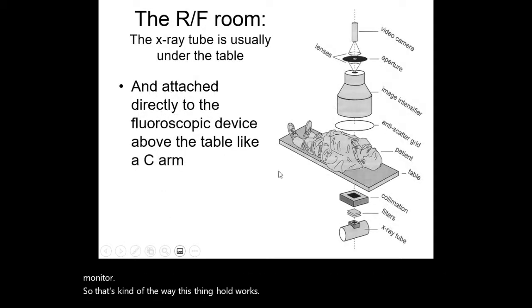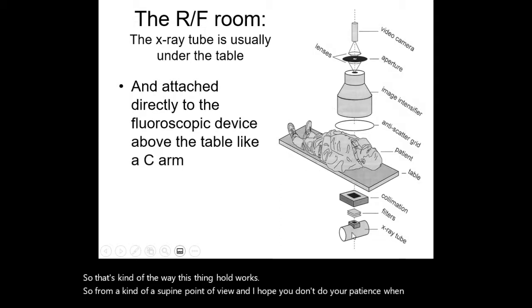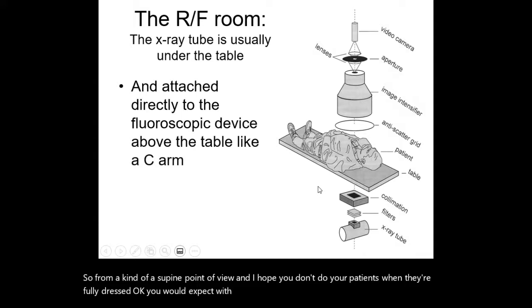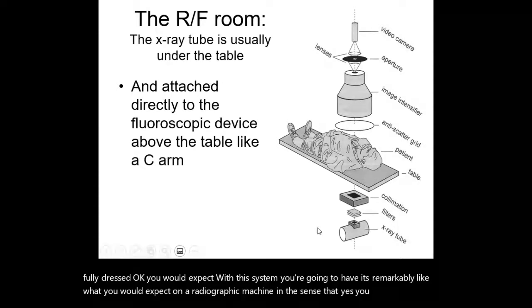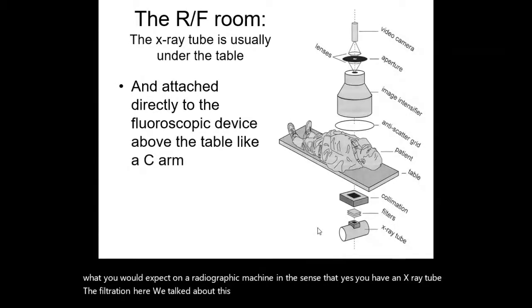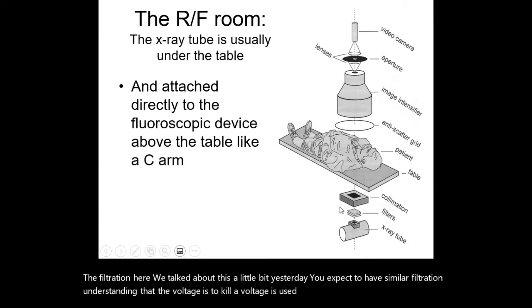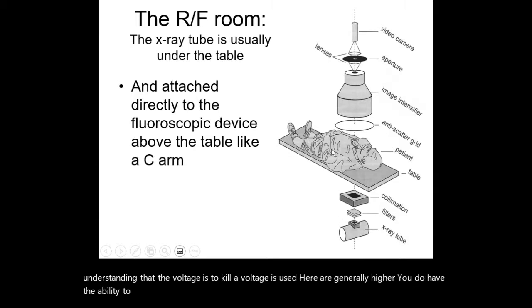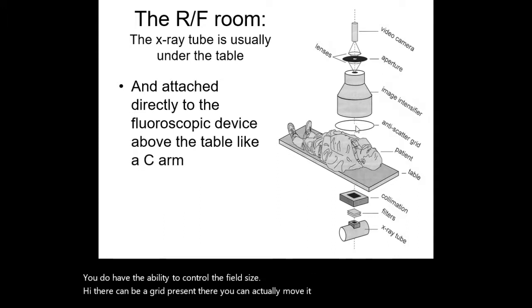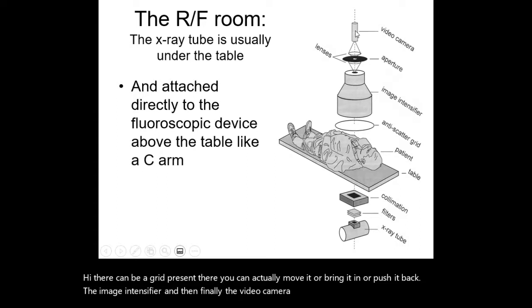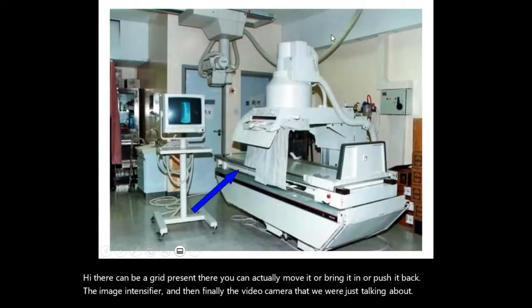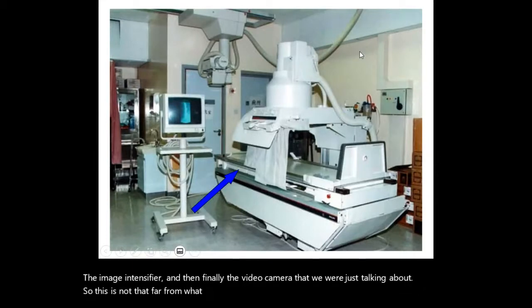So from a supine point of view, and I hope you don't do your patients when they're fully dressed, you would expect this system to be remarkably like a radiographic machine. You have an X-ray tube and the filtration we talked about yesterday, understanding that the kilovoltages used here are generally higher. You can control the field size, there can be a grid present, and you can move it in or push it back. Then the image intensifier, and finally the video camera we were just talking about. So this is not that far off from what you're used to seeing, assuming you've seen enough machines.